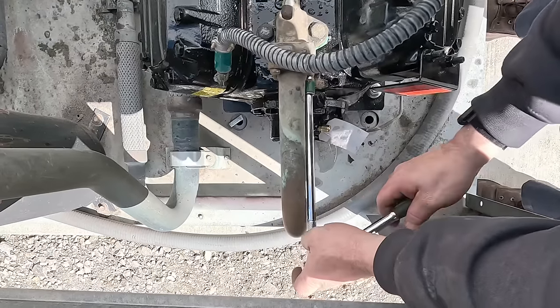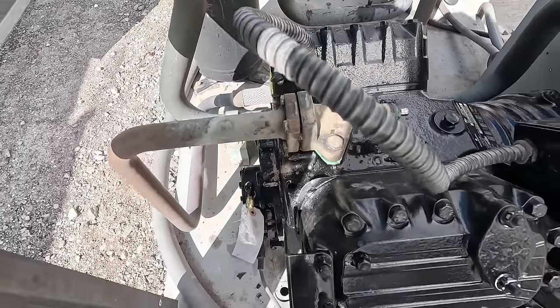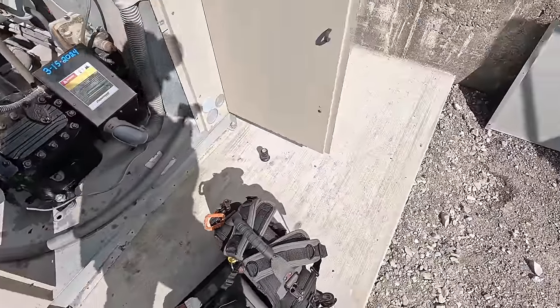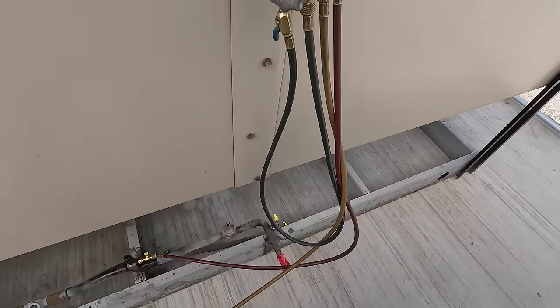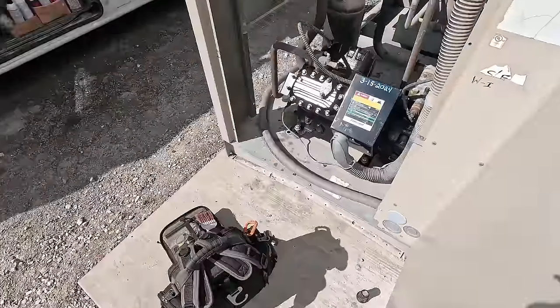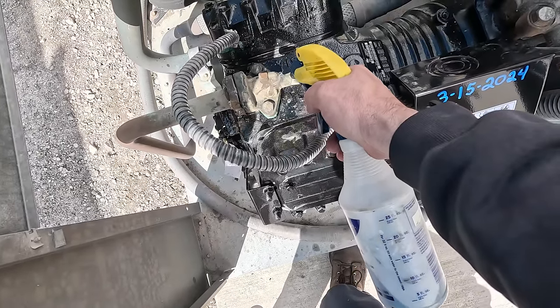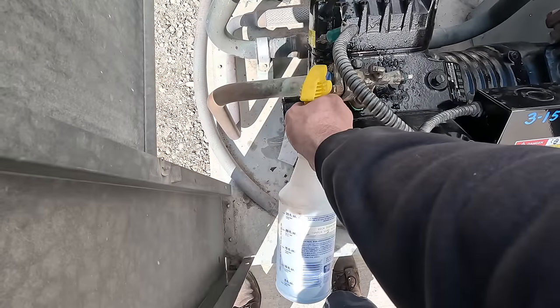Oh wow, it's not even tight. So it's a funny-looking flange because it looks like it kind of gets thin in the middle and goes out on the edge. Let's go ahead and squirt that again. I don't want to lose my nitrogen — otherwise I'd just throw a seal on it right now. I'm pretty sure I had an extra circular seal that would fit just fine, but I don't want to lose my nitrogen. Nice and solid stream. A little there — a little on the packing area. Let me shoot a little bit here on the front.